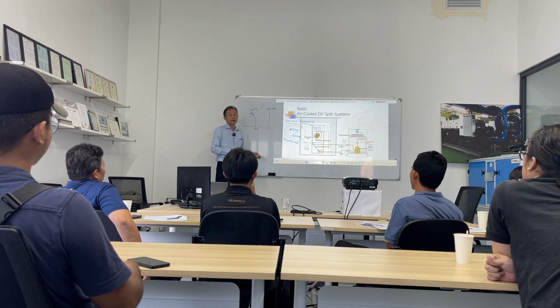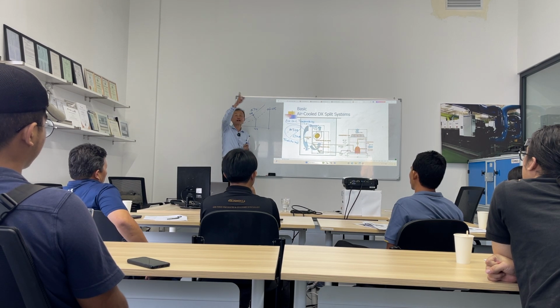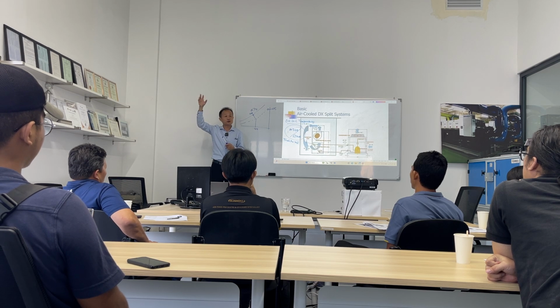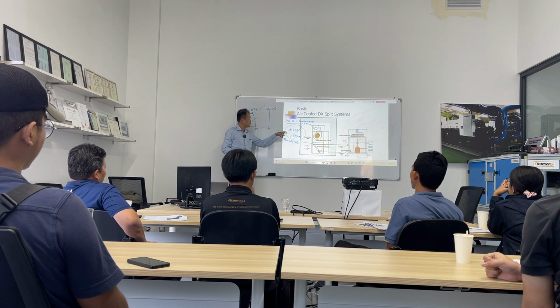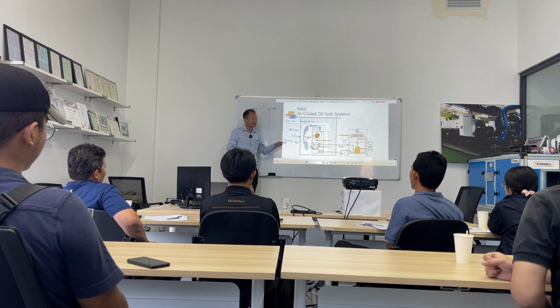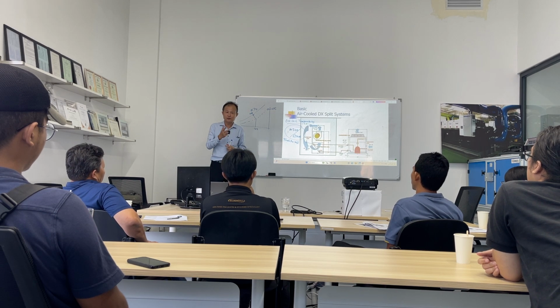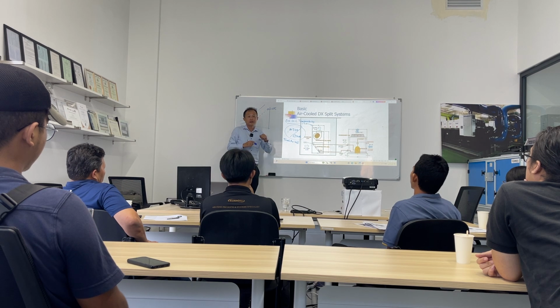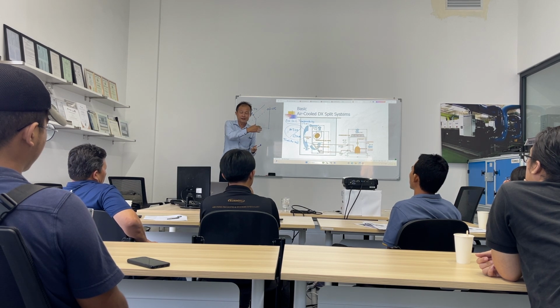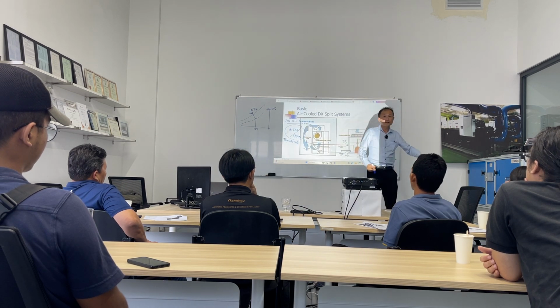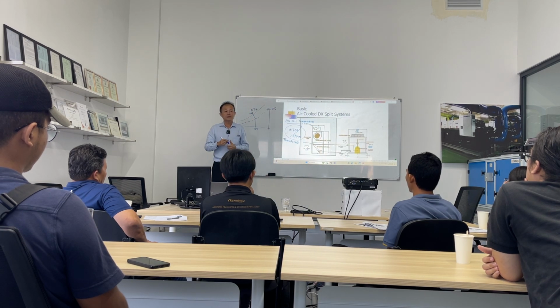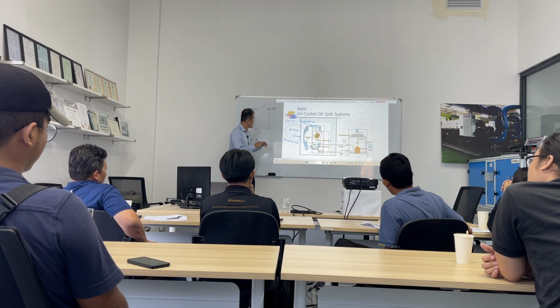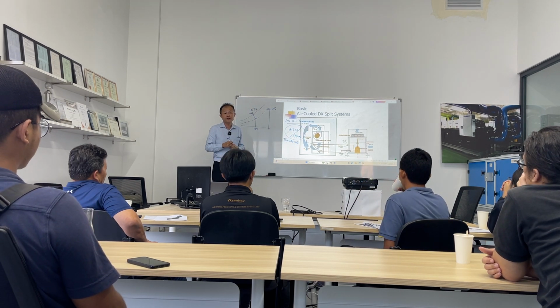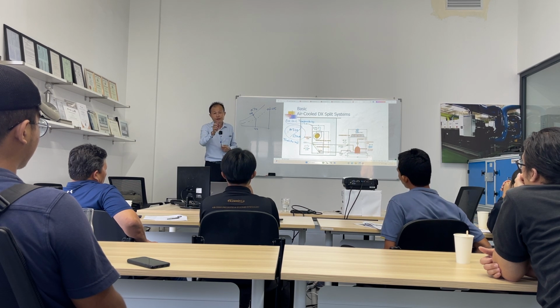That's why a lot of consultants in their design, if they use a DX system, they have calculated, for example, using a heat load calculation, this is maybe 1 horsepower or 10,000 BTU, they will normally multiply by 1.15 in their specifications to account for this type of overrated capacity by the supplier. I think that is important, no? But consultants in their standard practice, if they use a chill water system, for example, don't mark up. Because for chill water systems, all the manufacturers have their standard software. They will select the cooling coils based on the software and also based on the actual on-coil conditions designed by the consultant. But you will be confused, you know why?